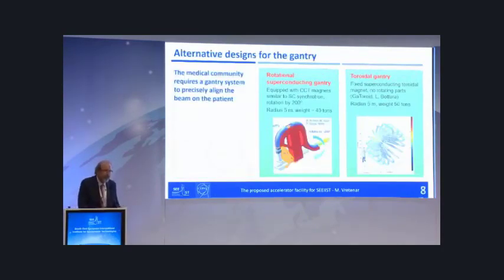For the gantry, also, nowadays, if in Europe a new gantry is built, it must be superconducting. For the gantry there is no, let's say, other option. You have to go superconducting. You have to profit of the advantage of superconductivity, either with a conventional rotational gantry, the first image. So this is a scheme that comes from the Terra team for a gantry equipped with superconducting magnets that rotates by slightly more than 180 degrees, where you can simply move the patient by 180 degrees. You save in the range of movement of the gantry, and it's a promising idea.